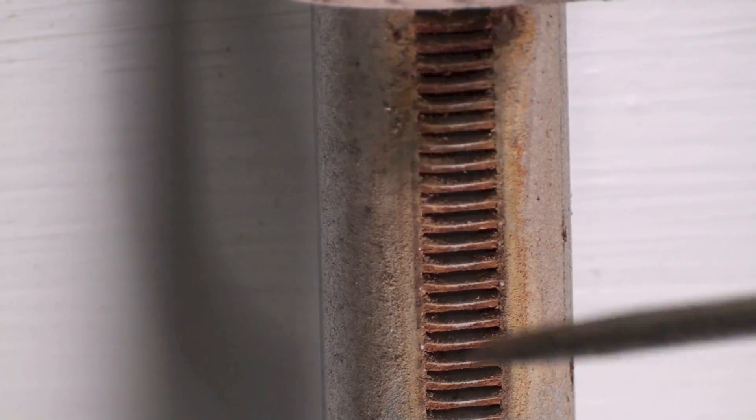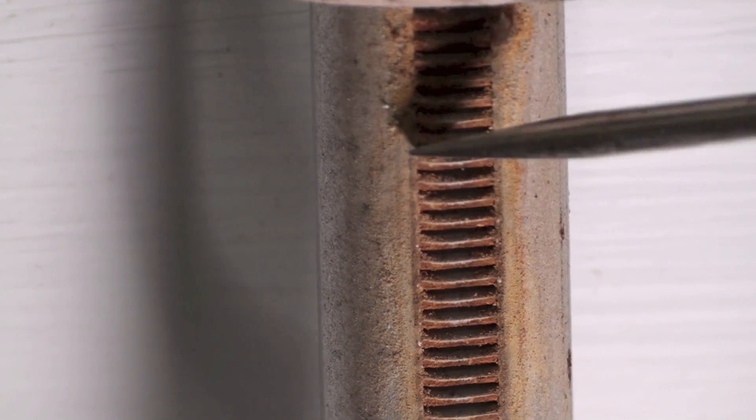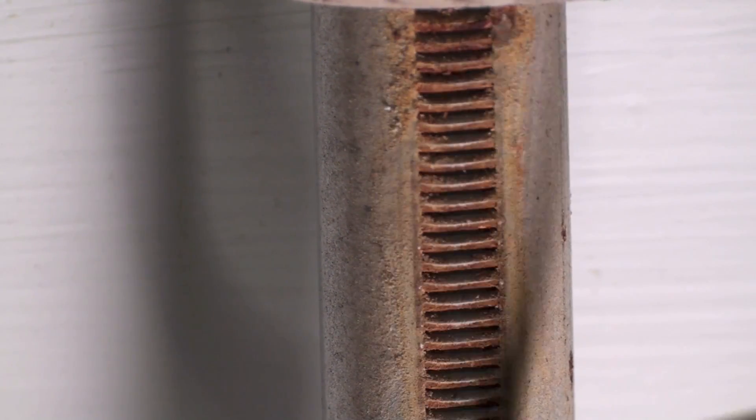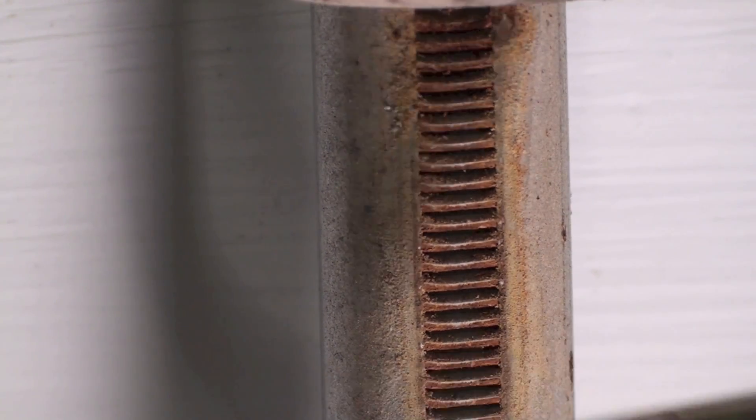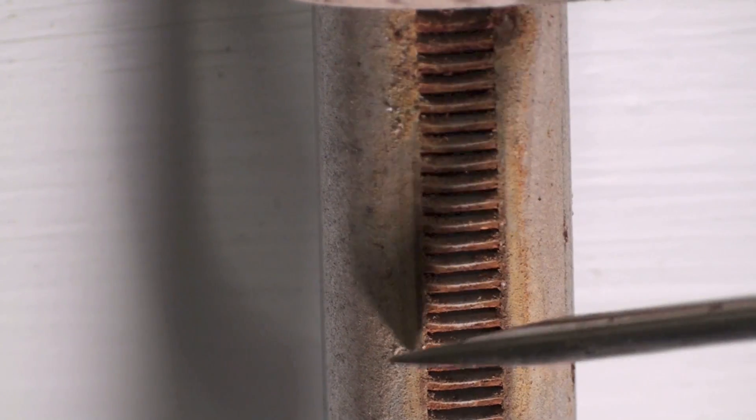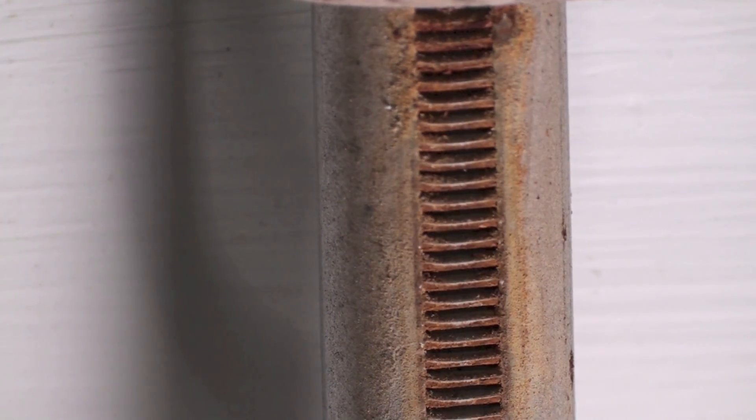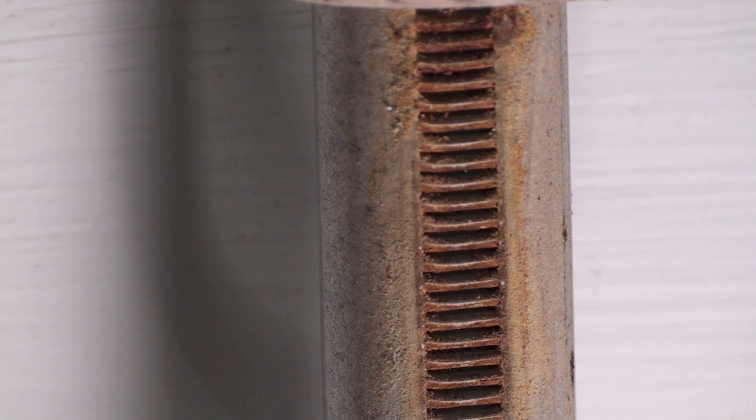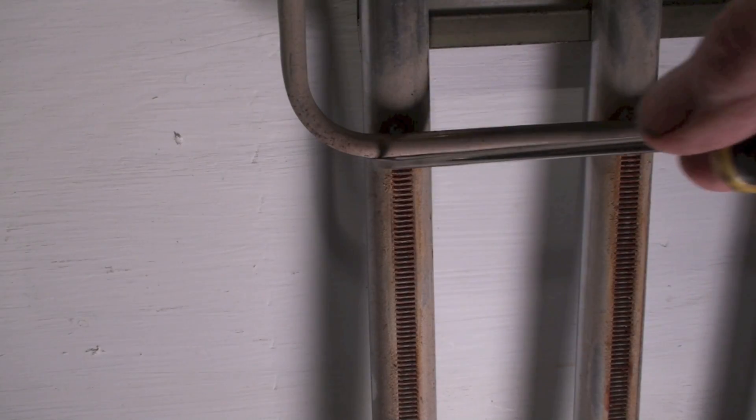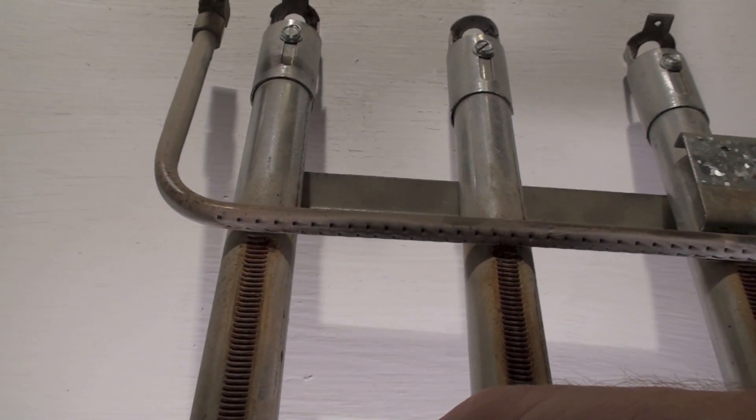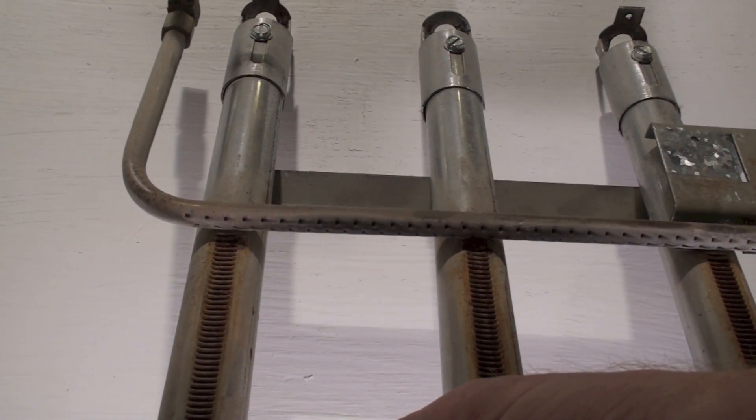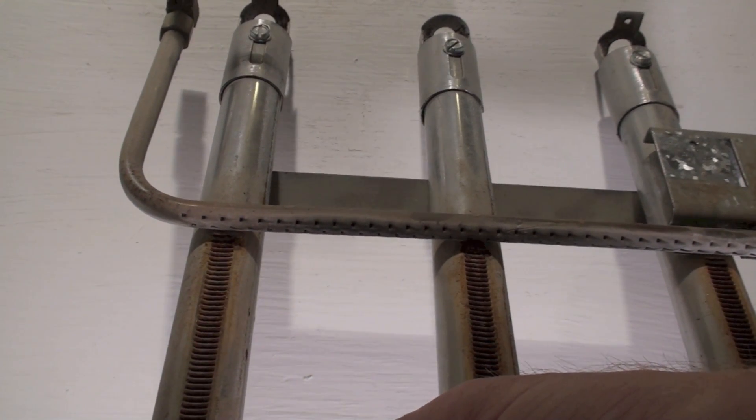There was a tendency in a lot of these things to rust out and they'd just be gone. Not so much in this furnace, but some of the other furnaces a little bit later, I think the fire is a little bit too cool and it tended to rust, and they had to make these things out of stainless steel. But make sure these are clean right in here. That's really about all there is to these things. You can run a brush across here because there's the tubes here. You can see those tubes, those holes in that tube there. Make sure those are clear.